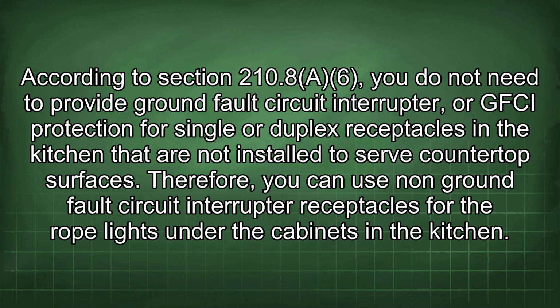According to Section 210.8(A)(6), you do not need to provide ground fault circuit interrupter, or GFCI, protection for single or duplex receptacles in the kitchen that are not installed to serve countertop surfaces. Therefore, you can use non-ground fault circuit interrupter receptacles for the rope lights under the cabinets in the kitchen.